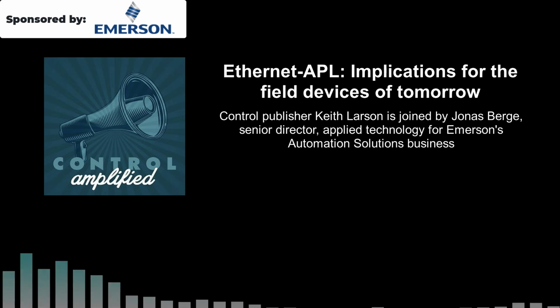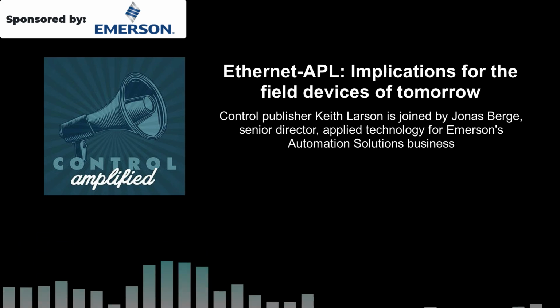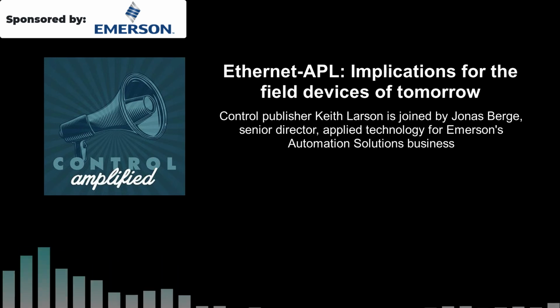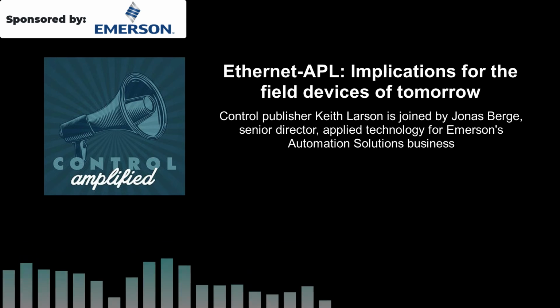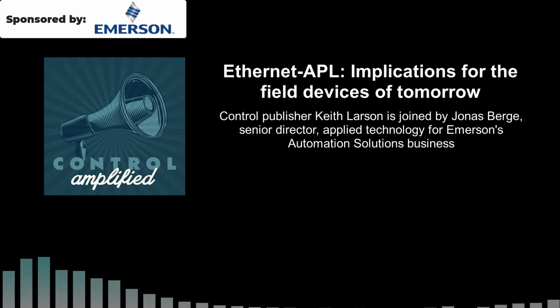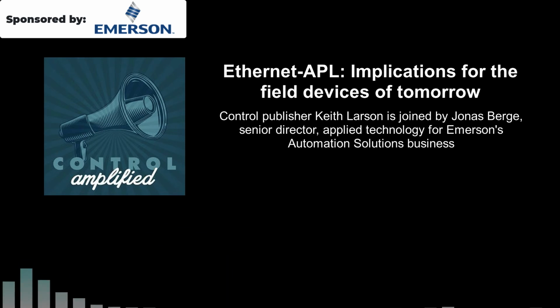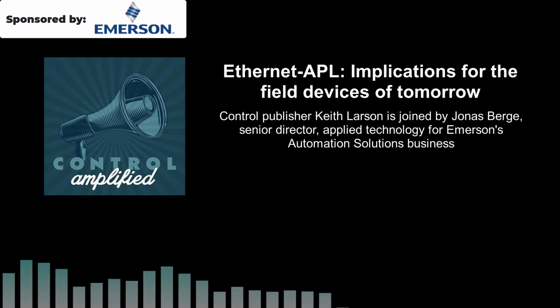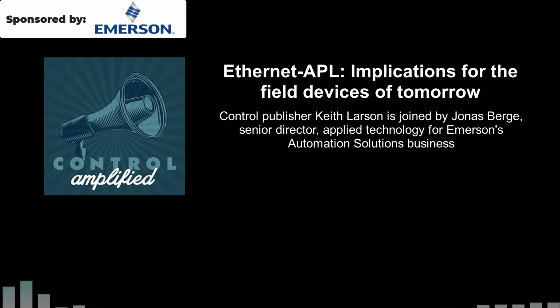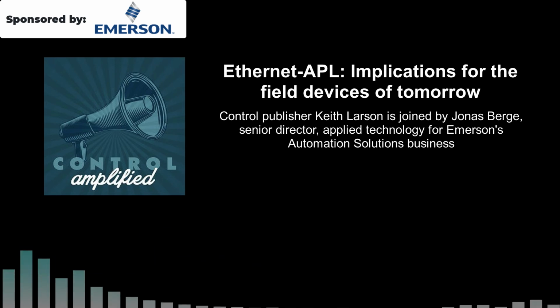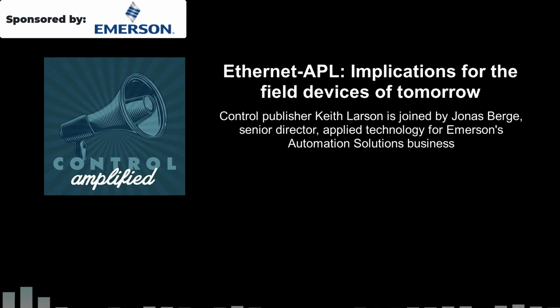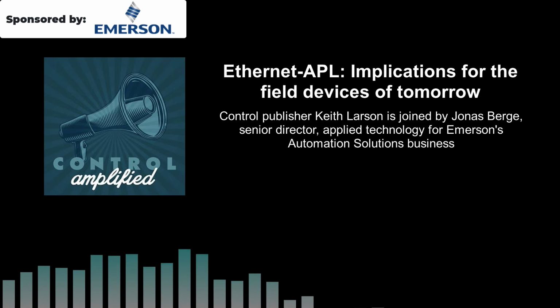And let's not forget about wireless sensors. Plants now use wireless sensors instead of portable testers for vibration, ultrasound leak testing, and ultrasound thickness for corrosion inspection, and instead of temperature guns and so on. Plants also put in wireless sensors instead of mechanical pressure and temperature gauges, sight level glasses, and variable area flow meters. These wireless sensors use wireless HART.